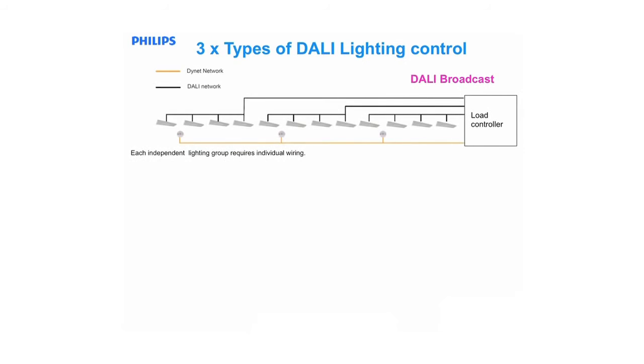We can see in the example here 3 lighting groups, and they've all been wired individually back to a load controller. A sensor is monitoring each of these areas, and they are connected back to the load controller using the traditional Dynalite network. The 3 areas in the example may be a single office, an open office or meeting rooms, and during the commissioning process the sensors will be logically assigned to each of those groups, and the controller will be able to respond to the messages from the sensors.